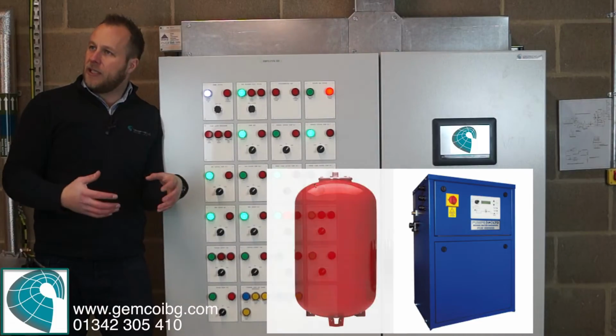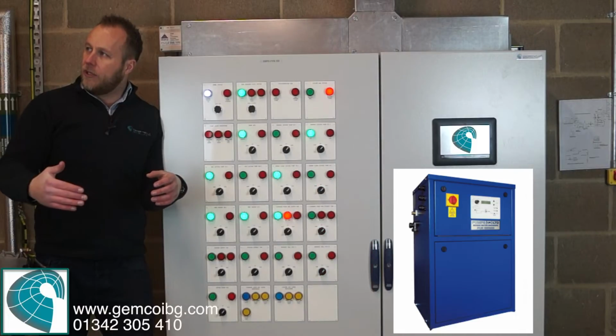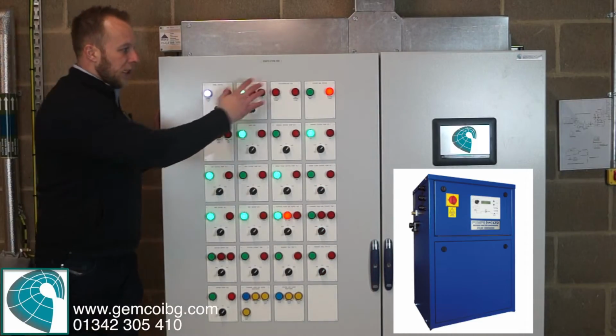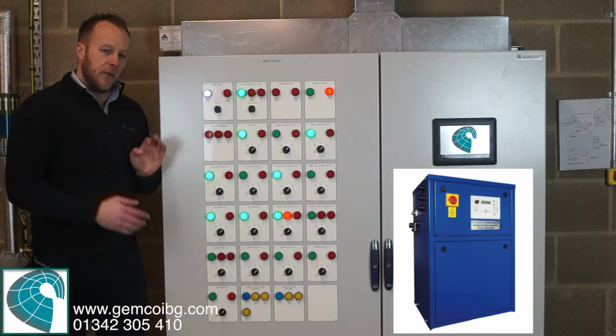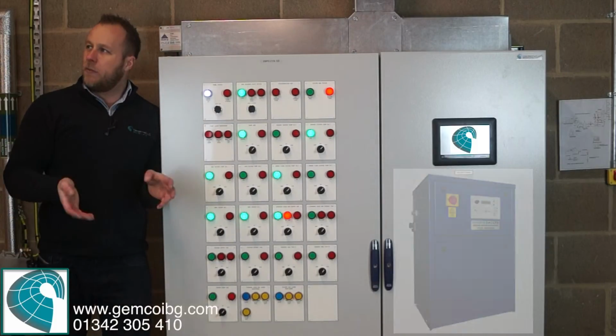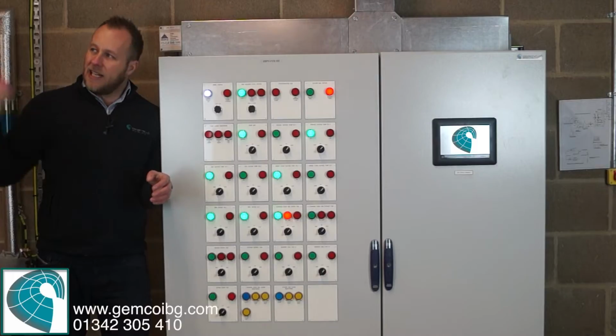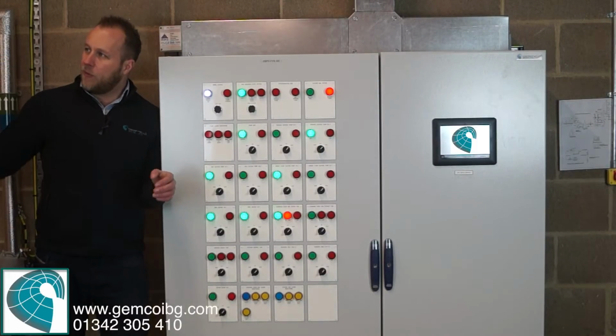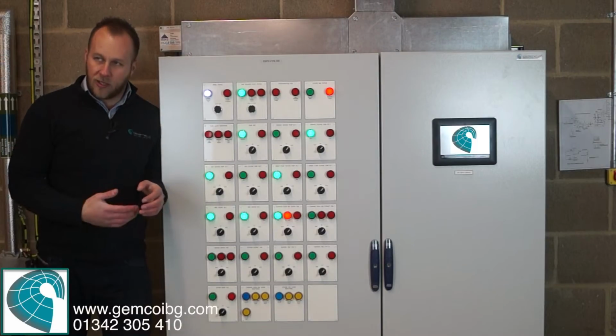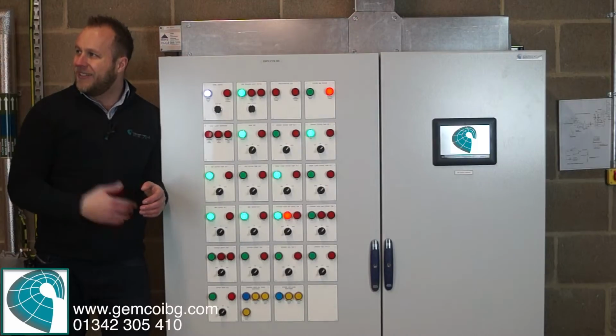And if it goes under pressure, it will inject some more pressure in off of the mains. And all we do is monitor that. The reason we monitor that is because we don't want your pumps running when there's a low pressure. Because say there's a leak somewhere, or a radiator comes off the wall or something, and you've got gushing water, the last thing you want to do is run pumps to fuel it.